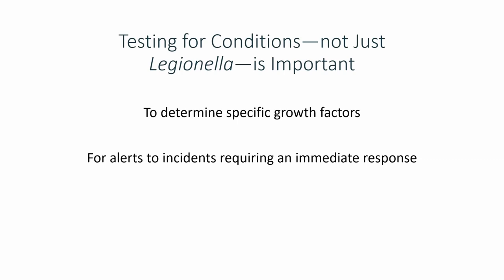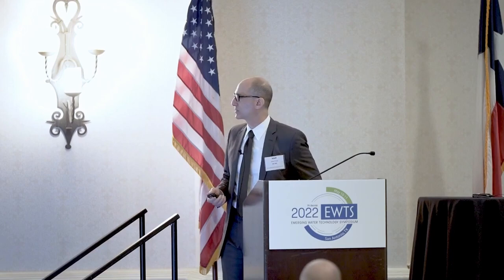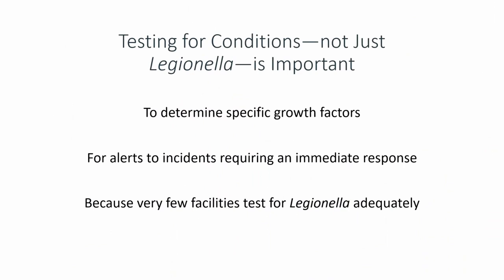— you're not testing for Legionella often enough. It's not practical to do that every day; it's too expensive, and the tests don't get analyzed quickly enough to respond immediately to those events. But monitoring conditions at the point of entry to a building can alert you to situations that need an immediate response. And this is probably the biggest reason.